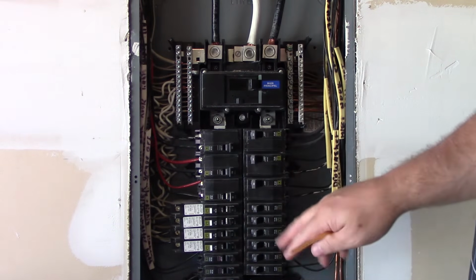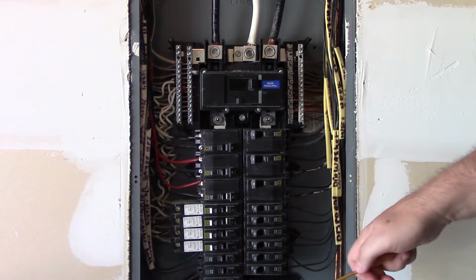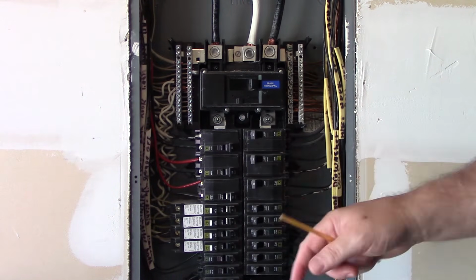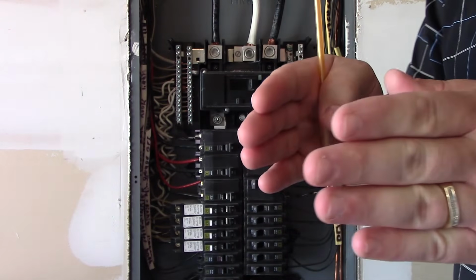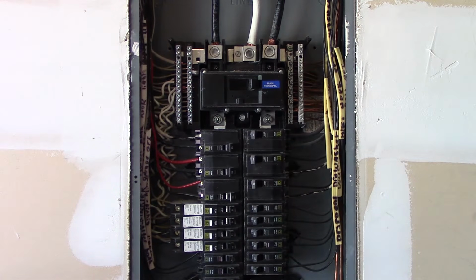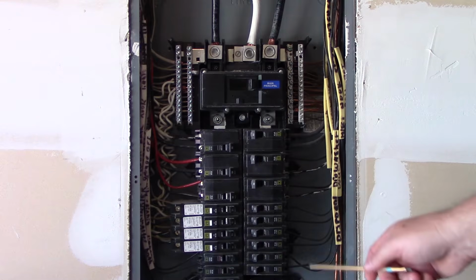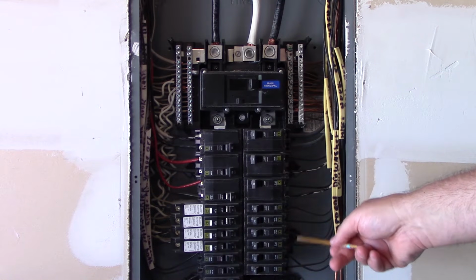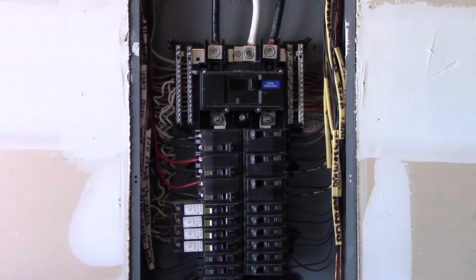If it says it, you can't see it because it'll be on the side, but you can tell by looking at the terminal. If it looks like a saddleback, which has two openings to allow two conductors to go in it, then you know that it's rated for two conductors. If you don't see that, and it's just a screw, then it's only rated for one conductor. So that's part of its rating.